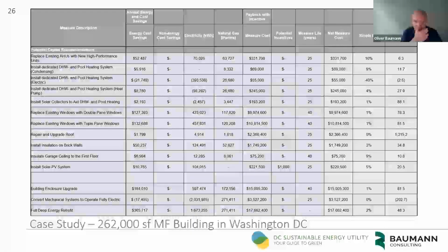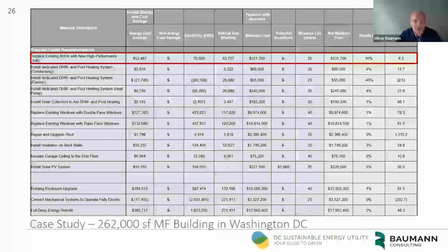So the first measure: replacing existing air handling units with new high performance units. We have energy cost savings of $52,000 per year. We indicate what we save in electricity, the fan power, and what we save in natural gas, the avoided energy going to heating coils from a gas boiler. We have the measure cost, the measure lifetime, and we calculate a simple ROI and simple payback of 6.3 years. It absolutely makes sense to implement that measure because that system has a lifetime of 25 years.